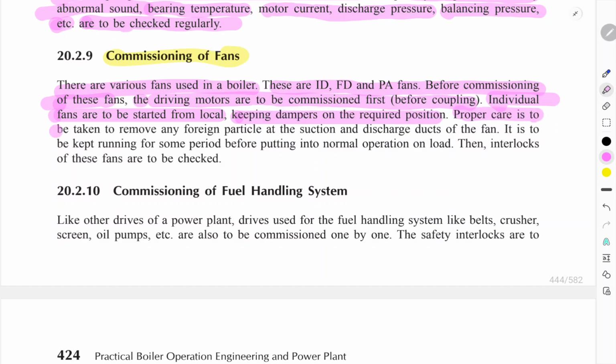Proper care is to be taken. Any foreign particles in the suction and discharge ducts of the fan are to be removed. The fan is to be kept running for some period before putting it into normal operation load. Then the interlocks of these fans are to be checked. Okay.